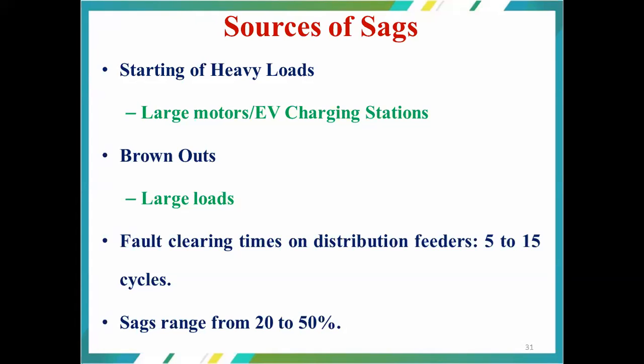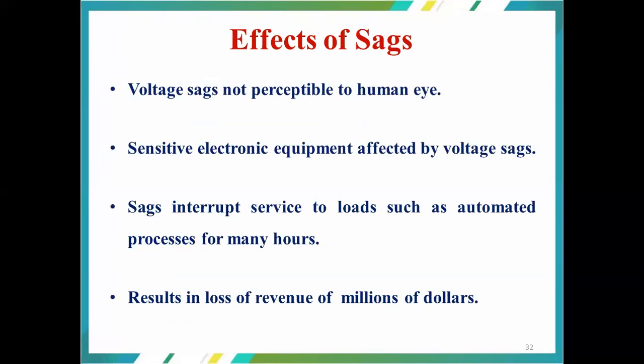And the fault clearing times on distribution feeders range between 5 to 15 cycles. Sags range from 20 to 50% of the rated voltage. The effects of these sags: voltage sags are not perceptible to the human eye, because if you are feeding power with harmonics or voltage with sags to any fluorescent tube or incandescent light, it is very difficult to notice with the naked human eye.